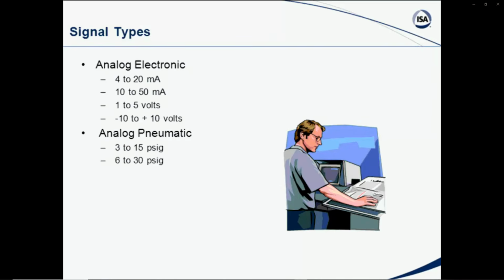So let's move into this part and talk about this to some degree and see if we can get a little bit of an idea of some of the questions that could come up with respect to what we could experience on the examination. Signal types. Right off the bat, of course, we have the analog electronic signal types that we can encounter or get involved with. We'll talk a lot about 4 to 20 milliamps. If you go out in the field at different locations, you may see 10 to 50, which was one of the types that sort of lost out in the milliamp wars.